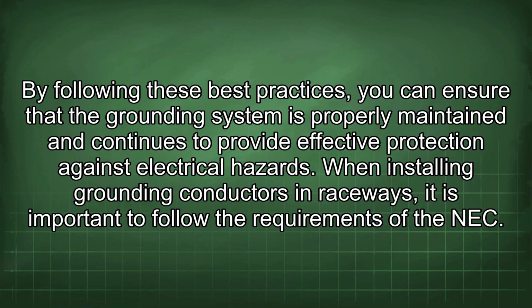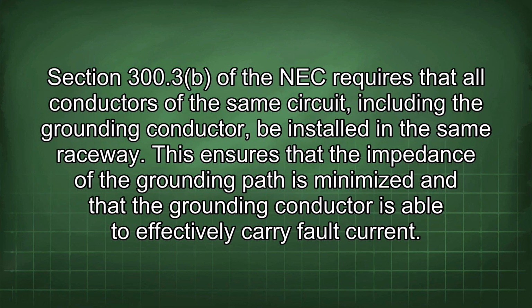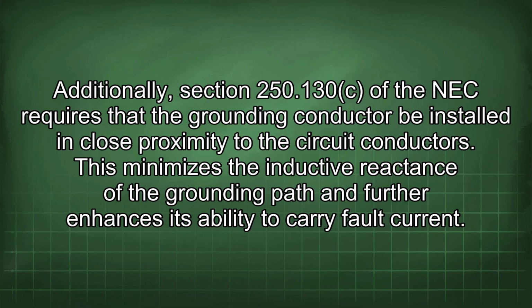protection against electrical hazards. When installing grounding conductors in raceways, it is important to follow the requirements of the NEC. Section 300.3 of the NEC requires that all conductors of the same circuit, including the grounding conductor, be installed in the same raceway. This ensures that the impedance of the grounding path is minimized and that the grounding conductor is able to effectively carry fault current. Additionally, Section 250.130 of the NEC requires that the grounding conductor be installed in close proximity to the circuit conductors. This minimizes the inductive reactance of the grounding path and further enhances its ability to carry fault current.